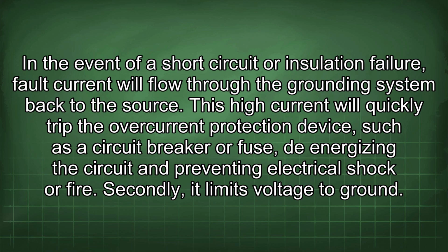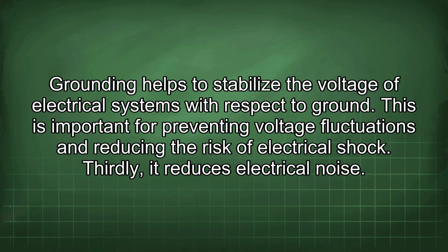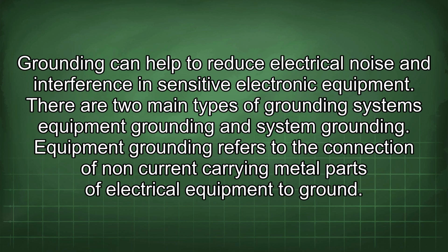Secondly, it limits voltage to ground. Grounding helps to stabilize the voltage of electrical systems with respect to ground. This is important for preventing voltage fluctuations and reducing the risk of electrical shock. Thirdly, it reduces electrical noise. Grounding can help to reduce electrical noise and interference in sensitive electronic equipment.